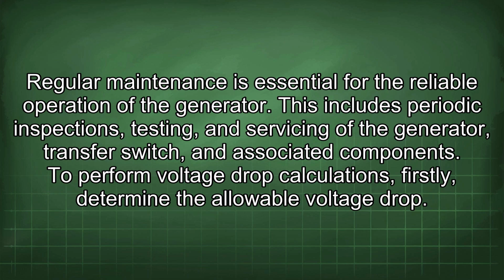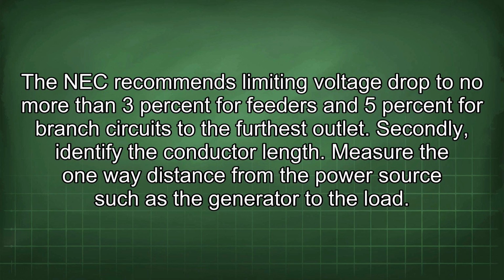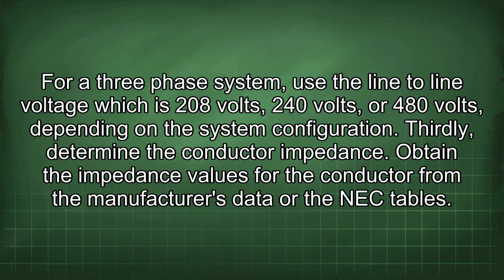To perform voltage drop calculations, firstly, determine the allowable voltage drop. The NEC recommends limiting voltage drop to no more than 3% for feeders and 5% for branch circuits to the furthest outlet. Secondly, identify the conductor length. Measure the one-way distance from the power source, such as the generator, to the load. For a three-phase system, use the line-to-line voltage, which is 208 volts, 240 volts, or 480 volts, depending on the system configuration. Thirdly, determine the conductor impedance.